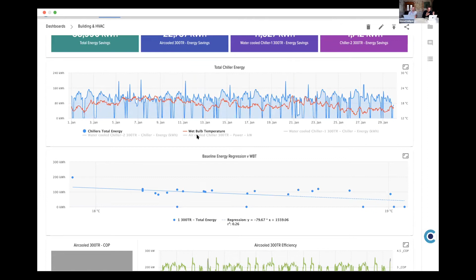As Sean mentioned, there's quite a number of other data points, weather station data points that we pull in as well. As this guy is a subject matter expert, he knows that wet bulb temperature should have a direct correlation on how those pieces of equipment are consuming their energy. So his first port of call was, again, visualizing that data - looking for any correlation straight off that trend graph, which to him there wasn't.